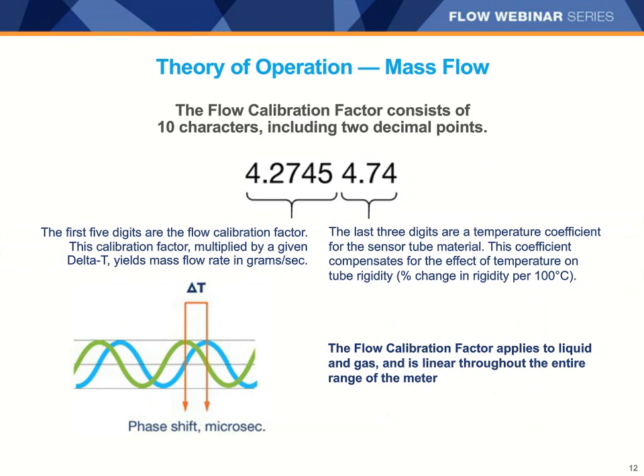The measurement of mass flow is very simple, as is the calibration. The flow calibration factor consists of 10 characters, including 2 decimal points. The first 5 digits are the flow calibration factor. This calibration factor multiplied by a given delta T yields mass flow rate in grams per second. So if a user wanted to shift the calibration by 10%, a simple 10% change in the calibration factor is made.